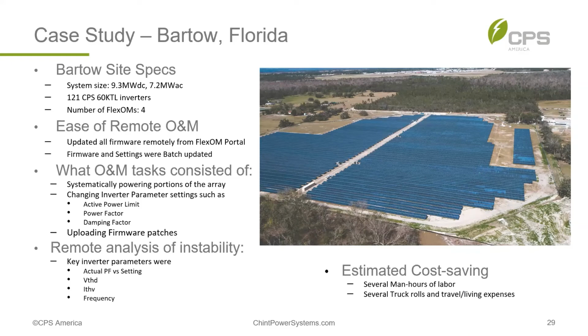The FlexOM was a lifesaver because it allowed CPS to configure a site with 121 inverters remotely and monitor the results. The configuration consisted of powering different portions of the array independently, changing parameter settings such as active power limit, power factor, and inverter damping factor.